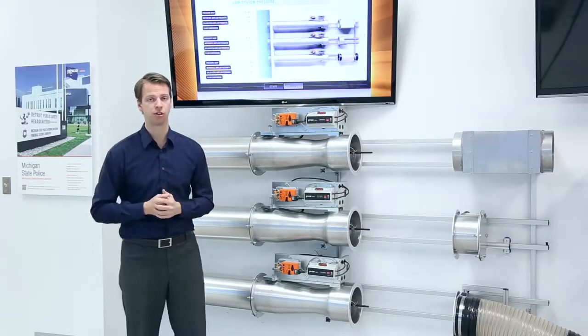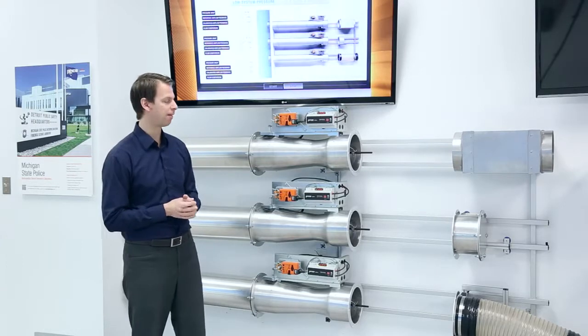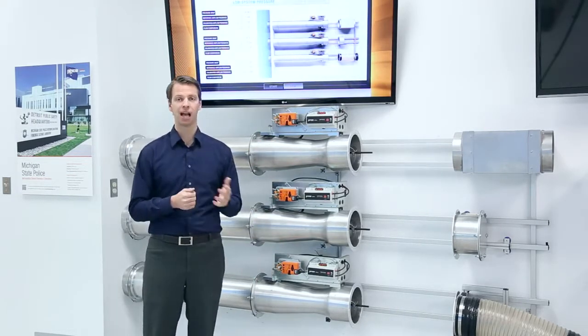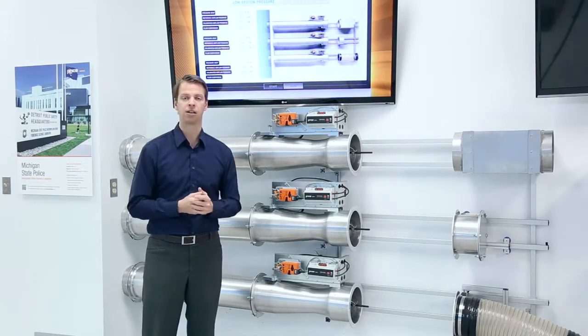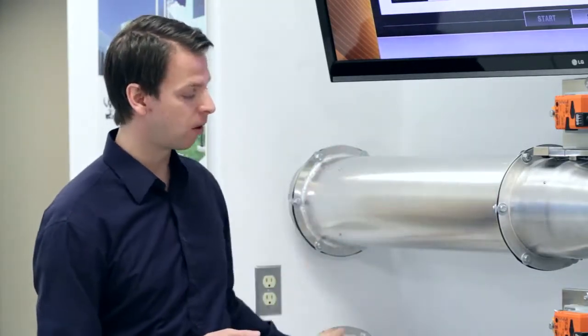So we actually have a demonstration to show you today. Here at Price Research Center North, we have our Venturi display wall. We have three valves. They've all been factory calibrated and characterized to provide an output airflow signal. In addition to that, we also have three reference airflow sensors just to verify our factory calibration for this demonstration.